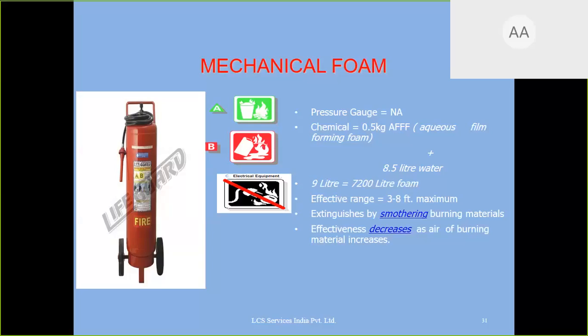Next is my mechanical foam. So mechanical foam contains three things, right? It contains a chemical known as AFFF, aqueous film forming foam, 0.5 kg. It contains water. This extinguisher has 8.5 liters of water, a chemical, and third, to become foam, we need chemical, water and air. Then only foam will be there. In this, there is no air. That is why no foam. It has only chemical and water.